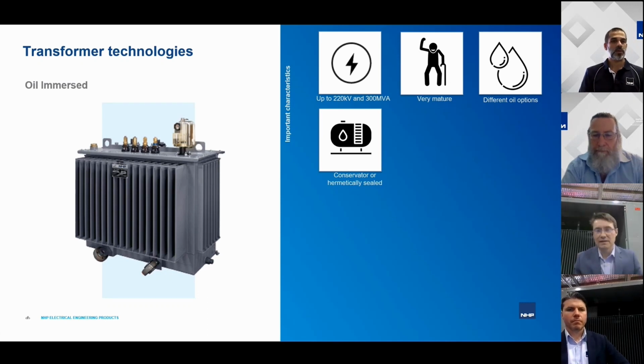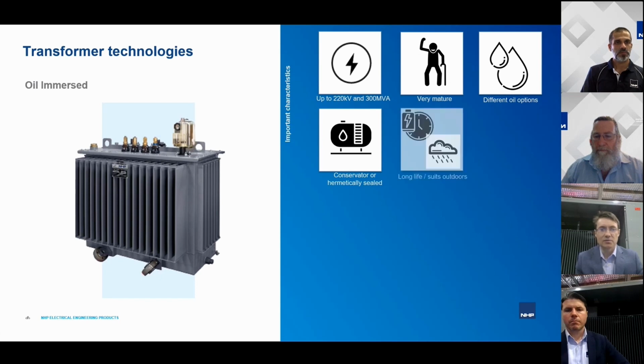Thanks, Kim. There are two main technologies within the oil transformer family. One is a conservator type, and the other is hermetically sealed. The hermetically sealed name tells us it's fully sealed. There's no contact between oil and the air. This technology is used predominantly in smaller power distribution transformers, which normally go up to 3 MVA, but we've seen that hermetically sealed technology going up to 6 to 7 MVA, and really the demarcation line there is where you can have welded fins. And this is where you can still have the hermetically sealed transformer.